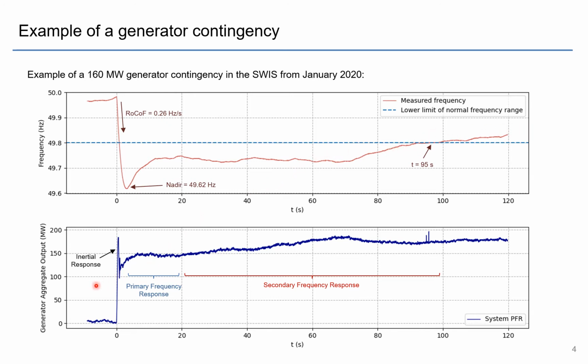And here you see an aggregated primary frequency response, and you see the inertial response of all the generators to begin with, followed by a primary frequency response, and then a secondary frequency response to bring the frequency back up to the operating band.